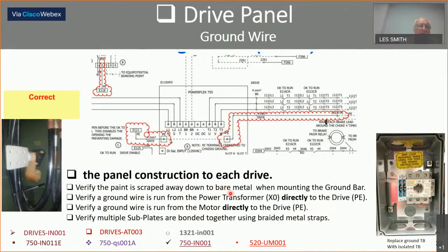More important to me is these notes here. Verify the paint is scraped away down to the bare metal when you put the ground bar in. Better yet, put a galvanized backplate in. Verify ground wire is run from the power transformer X0 directly to the drive PE. And then verify the ground wire is run from the motor directly to the drive PE. Verify sub-panels are bonded together using braided metal straps. The noise we're talking about prefers fine wire as opposed to solid wire.